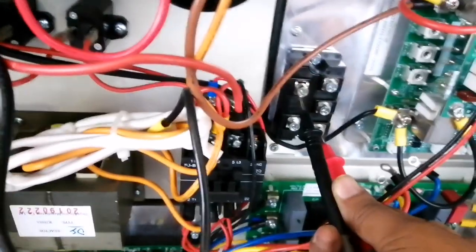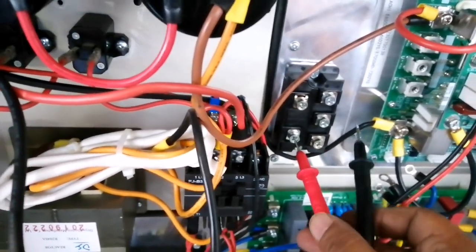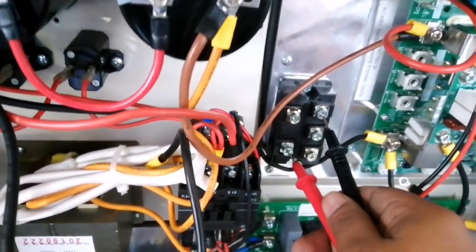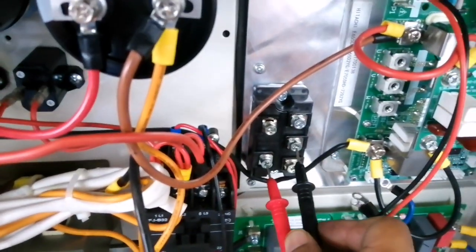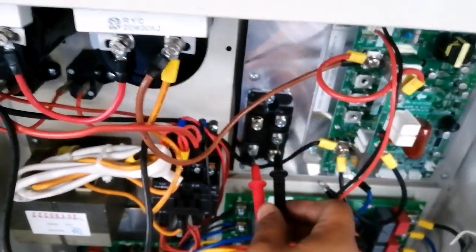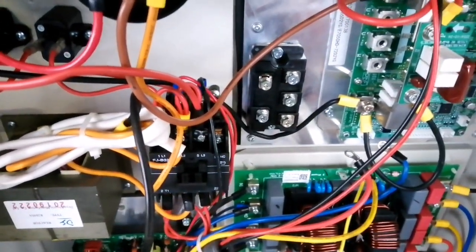Now for the same process on the negative side: put the positive pen on the negative terminal and touch U — it shows 488. Touch V — you get 484. Touch W — it shows 487. The diodes inside the rectifier are OK.